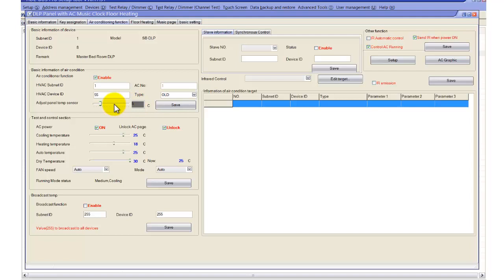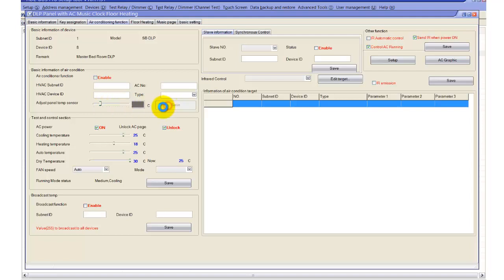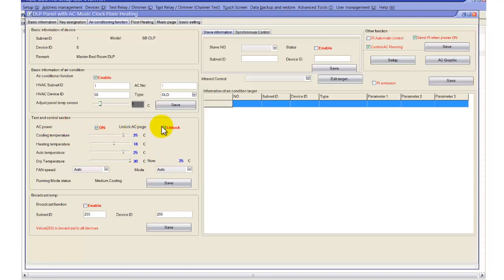Here we have temperature adjustment for the panel temperature sensors. We can calibrate the DLP panel temperature sensor by setting values like minus 5, plus 4, plus 5. In the test and control section, we have the AC power option, and you can lock or unlock the page. There are cool temperature set points, heat temperature set points, auto temperature, dry temperatures — all configurable based on your requirements.